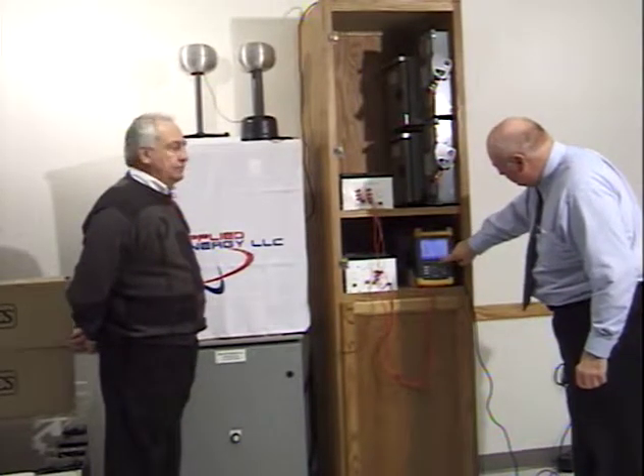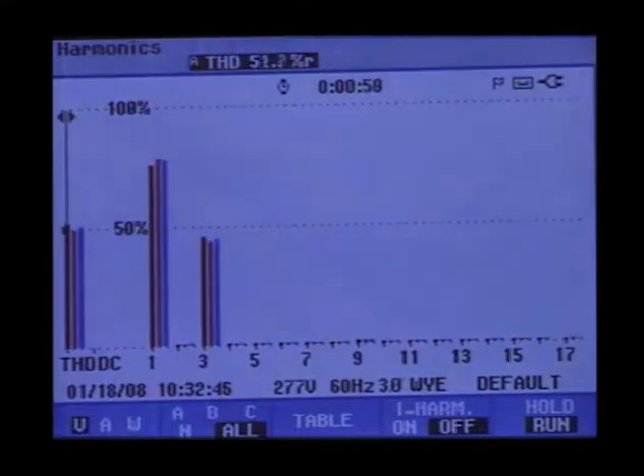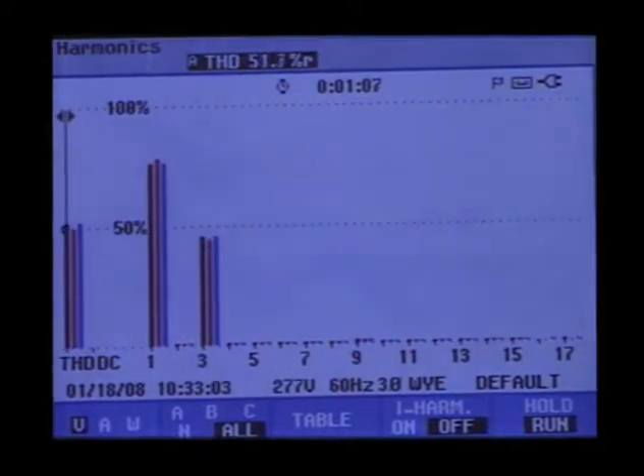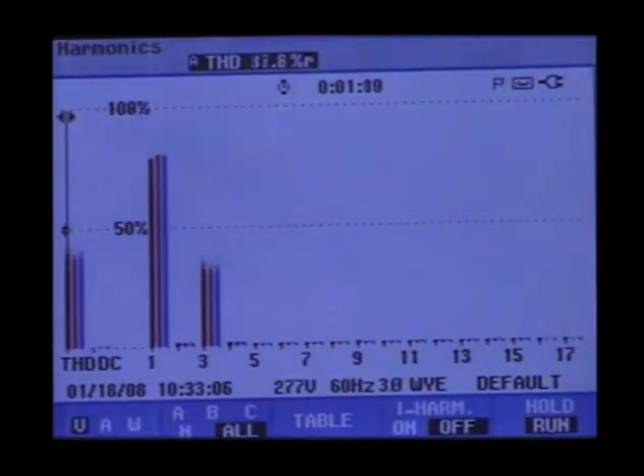As we're looking at this particular live shot of the harmonics, we're finding that in this case, this drive is putting out a significant amount of 3rd harmonic, and we'll look at voltage in a bit. I have a disconnect to turn on our small version of Phaseback, calling a dry voltage stabilizer. And we've had an instantaneous reduction from about 45% harmonics down to 10.